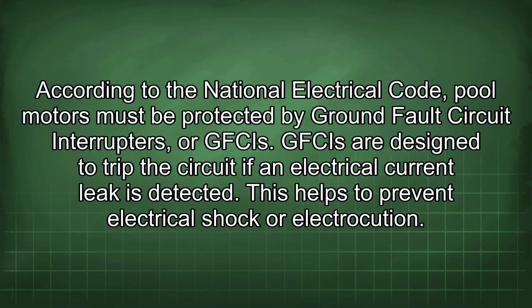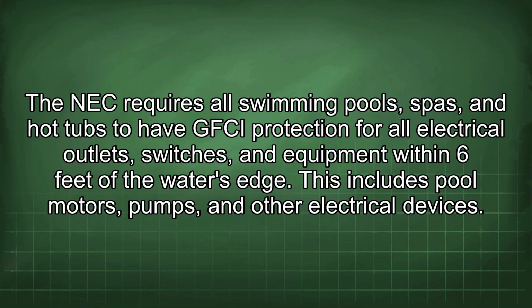According to the National Electrical Code, pool motors must be protected by ground fault circuit interrupters, or GFCIs. GFCIs are designed to trip the circuit if an electrical current leak is detected. This helps to prevent electrical shock or electrocution. The NEC requires all swimming pools, spas, and hot tubs to have GFCI protection for all electrical outlets, switches, and equipment within 6 feet of the water's edge. This includes pool motors, pumps, and other electrical devices.